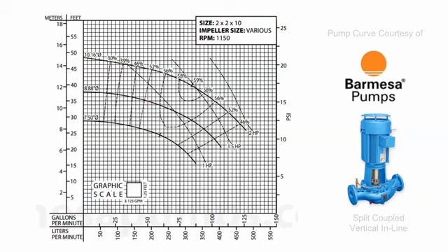Now, this particular pump curve also shows the efficiency, but in a somewhat different format. What we see here is the efficiency is laid out by these tick marks: 30, 39, 46, 52. These are the percentage of efficiency for that particular spot on the performance curve. And these kind of have curves themselves, so the most efficient that this pump can be is the center line here of 59. And again, as I mentioned, you can see that on this pump it's relatively true, and this line goes from here down to here as the most efficient point for each particular impeller trim. And that's relatively the center of that particular performance curve.